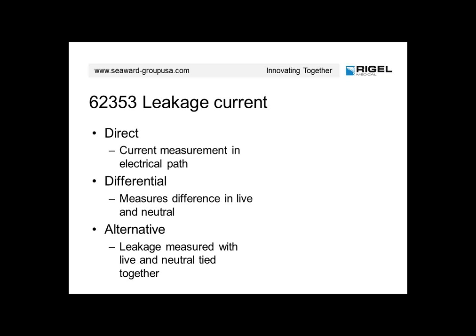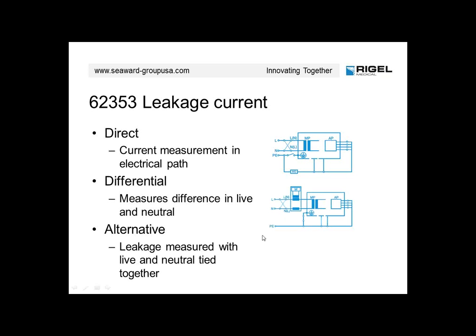Alternative almost would look like a hipot test where the input line or the applied parts are tied together, hit with a voltage, the 500 volts, and then the leakage current identified that way. There's a little diagram for direct. The differential, you'll see the current transformer and the measurement device, and alternative where the input or the applied parts are tied together.